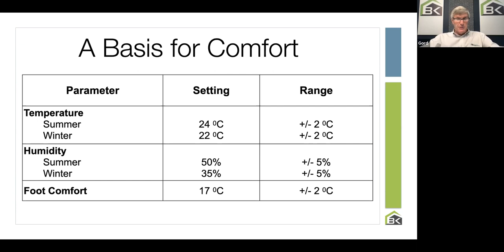I'm interested in the humidity numbers too. Robert, you'll know this, the Sterling chart comes from 1976 or so, and was recently validated during COVID. The idea is that occupant health is best between 40 and 60 percent, and that's a great number. But in Canada, certainly in Calgary, northern Alberta, and northern Ontario, we can't do 40, it would be too much stress on windows and cause condensation. So we're more like 35 plus or minus 5, nudging up to 40 in the wintertime, is where we want to get to. But those are the kinds of levels.